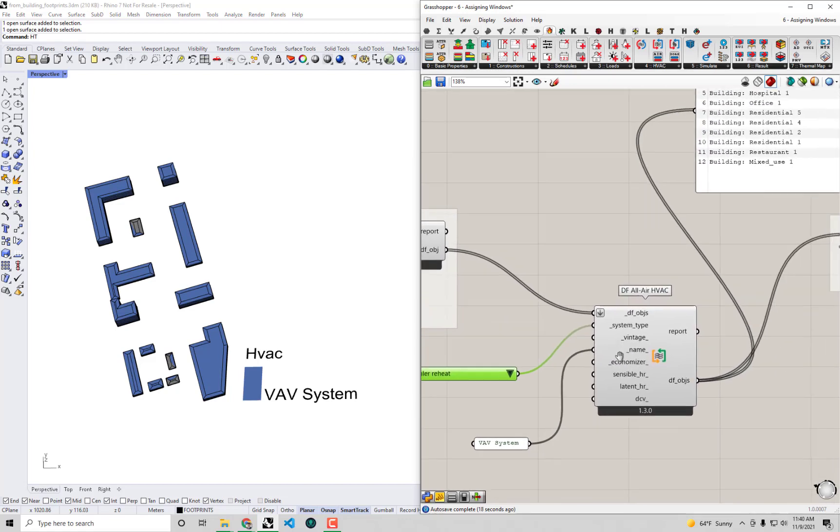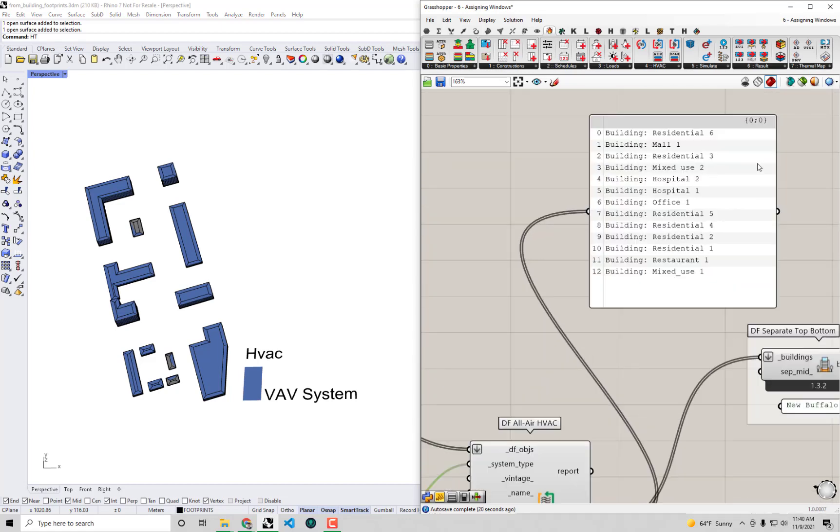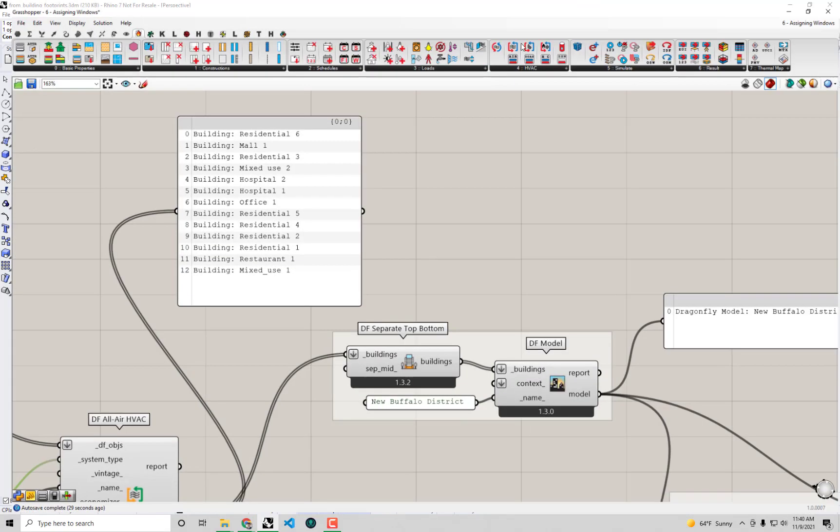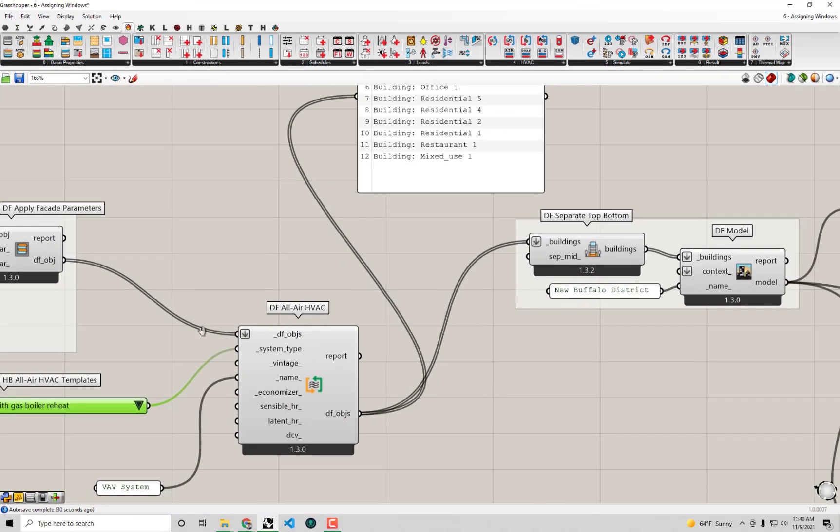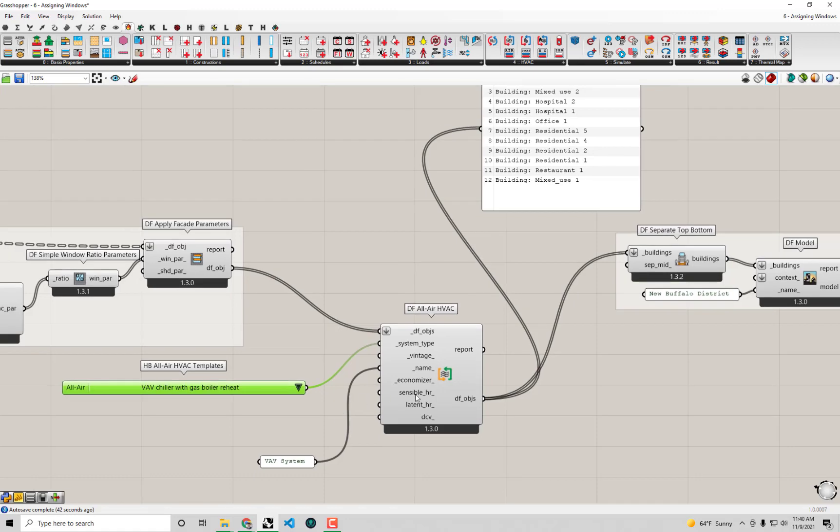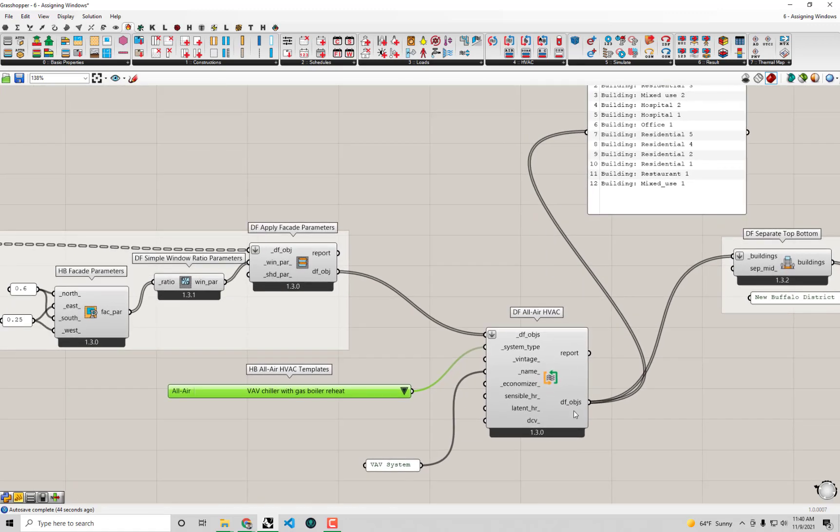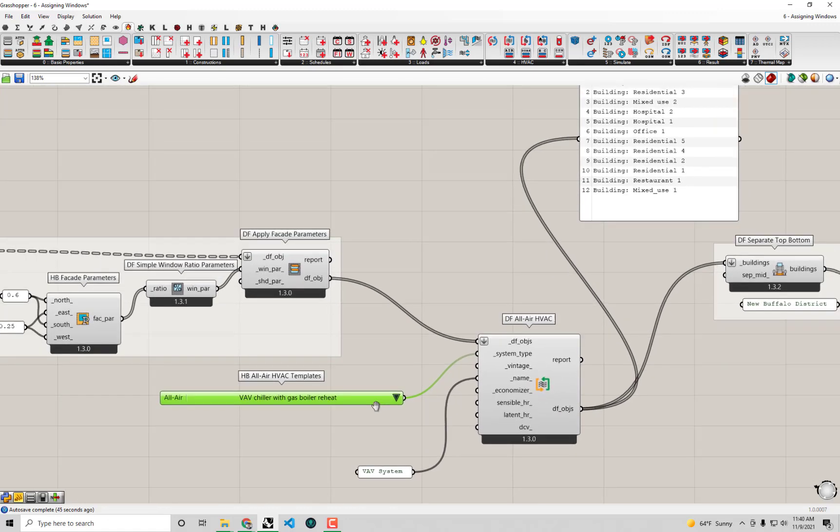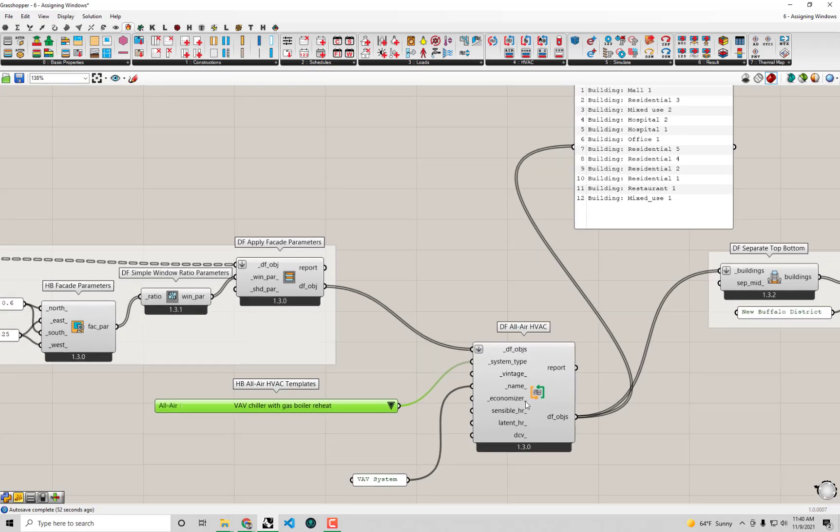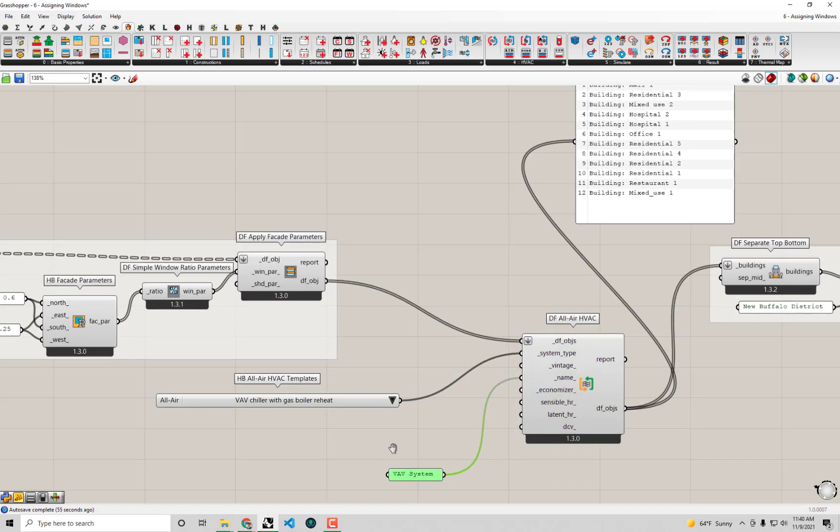And actually taking a second and looking at this, you guys will see we have a bunch of different types of buildings here. Some of them are commercial, but some of them are residential, and you heard me just say like a minute ago that this VAV chiller with gas boiler reheat is really only intended for the case of commercial buildings—commercial buildings that are usually of a certain square footage or larger or a certain number of stories, more than five stories would get this template. So at the least, maybe we'll say that we should apply a different type of HVAC system to the residential buildings here.